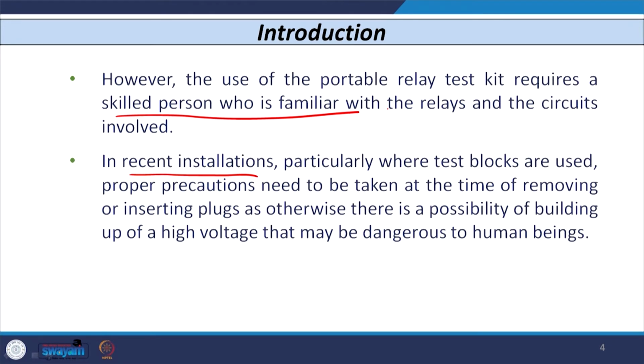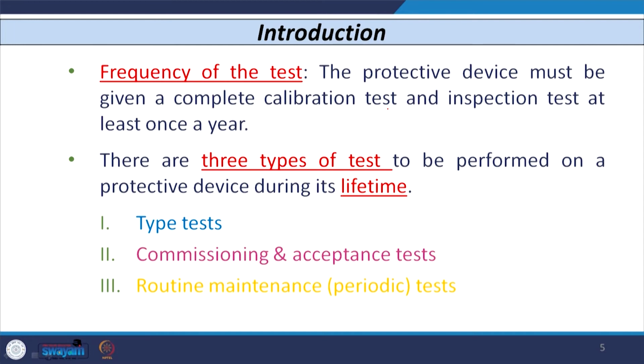Similarly, you have to take care of several other things also when you carry out the testing of relays using a standard relay test kit. Okay, so let us consider the frequency of the test, which is also very important, because the interval at which we need to test the protective device or relay is a very important point. A protective device must be given a complete calibration test and inspection test at least once in a year.